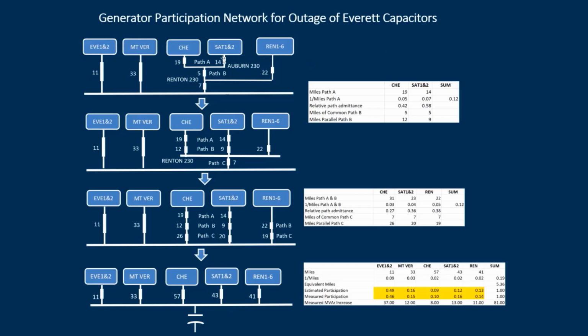Previously, we showed you the technique of doing a parallel path reduction. We showed you how we could take the path of 19 here and 14 here and combine that and reduce it to a single path. In this case, we have to do the reverse. We have to do a parallel path expansion. We have to take the link which has got the common flows of Chehalis and Satsop and expand that into two separate links which have the individual flows of both those generators. So let's look at the process to do that.